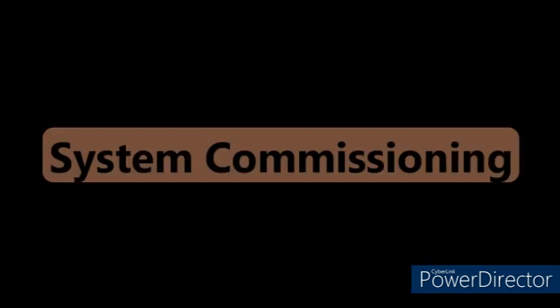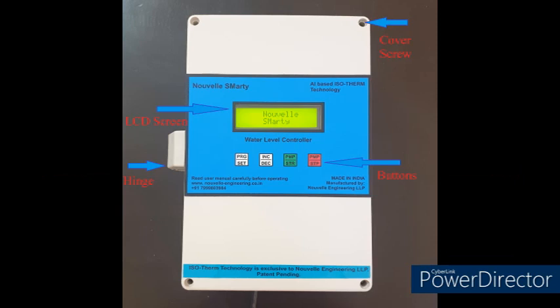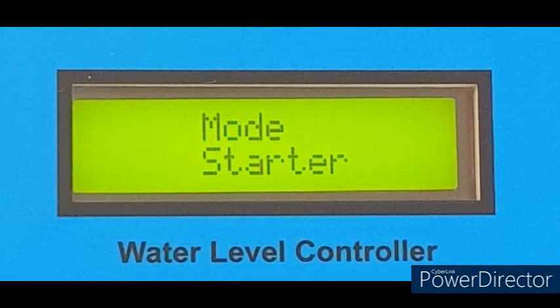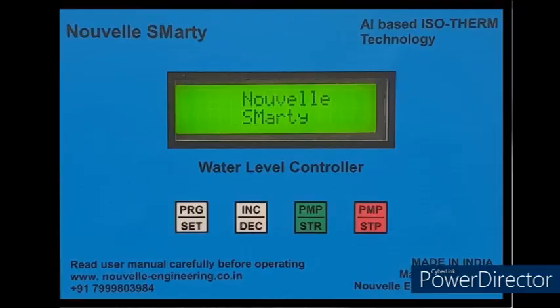Commissioning of WLC. Now power up the WLC panel while the pump feeder is still not powered up. Check all the parameter values displayed on the main screen, particularly FDR mode and operation. If you want to change any parameters, press and lift slowly the PRG, set button to navigate through different menu items. Once the required menu item is displayed, press and lift slowly the INC, DEC button to navigate through different values of that menu item. Once the required value of a particular menu item is displayed, long press the PRG, set button for 5 seconds, till it flashes saved, to save the displayed value.